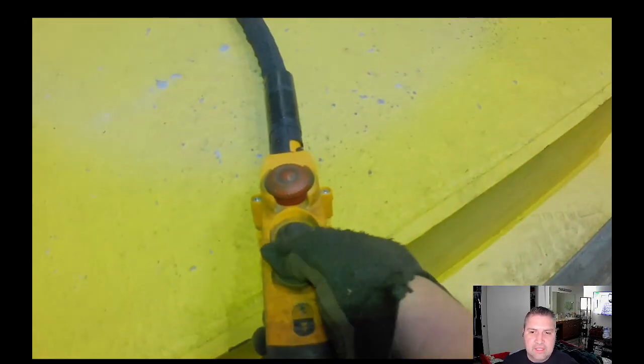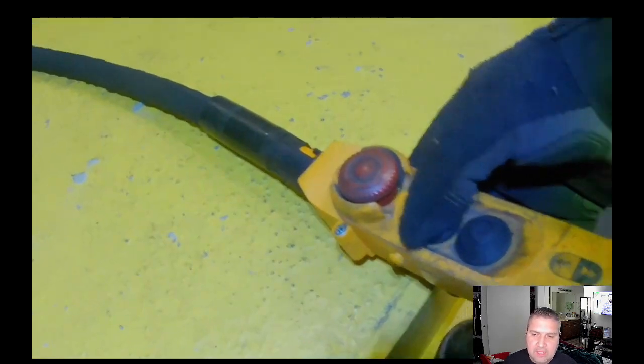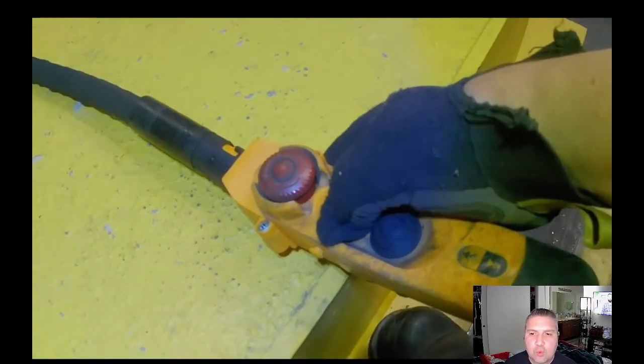It also says part of the process to repair this code is to check the mains connection and/or fuse link, check the connection cable for interruption, check the mains connector in the service enclosure, reduce the load to the permissible load capacity, and ensure appropriate mains voltage. We went ahead and did all that, and the code was still persistent. So that's a little window into what that code is. I have to move from there and find where the specific issue is.